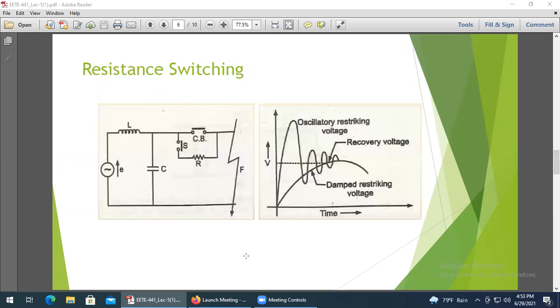You should use the resistance switching where you will observe that the chance of rising the frequency of the TRV is very high. Okay, because the high frequency TRV will always create some problem for you. Always remember that. So in order to provide a precaution to the circuit breaker, the resistance switching is provided, nothing but just to suppress the high frequency component from the TRV, resulting in a decrease in the rate of rise of the TRV as well as an increase in the breaking capacity of the circuit breaker. More or less, the circuit breaker safety can be provided by this resistance switching in some special cases.